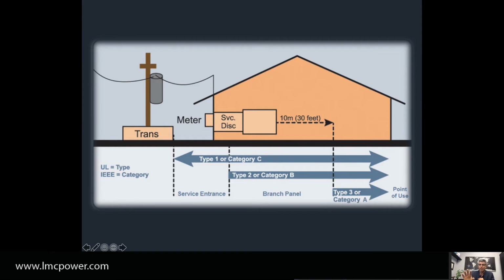Let's look at where it says point of use. Point of use is around 50 kA of protection, and that's considered type 3. So some of your customers may recognize category C, B, or A, or the terminology could be type 1, type 2, type 3. So don't get confused on that. It's the same thing. Type 3 is category A. That means it's designed close to the load, around 50 kA. Category B, or type 2, is around 50 to 100, 100 to 150 kA of protection.